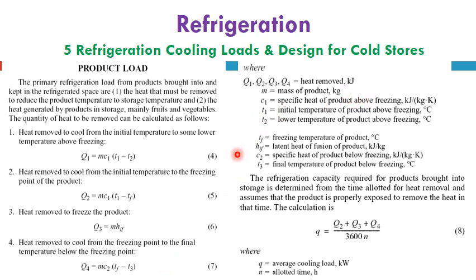Here we can find this nomenclature, where Q1, Q2, Q3, Q4 are the heat removed in kilojoules, M is the mass of the product in kilograms, C1 is the specific heat of the product above freezing in kilojoule per kilogram Kelvin, T1 is the initial temperature of the product above freezing in degrees Celsius, and T2 is the lower temperature of the product above freezing, also in degrees Celsius. Tf is the freezing temperature of the products, which can be found in chapter 8, the temperature at which this product freezes, maybe below 0 degrees, maybe -2, -1, -5, according to the chemical composition and the water content inside these products, especially for fishes, meats, shrimps and chicken.